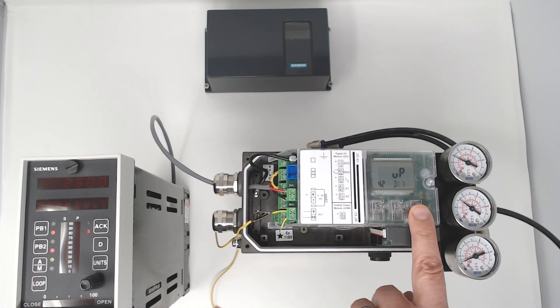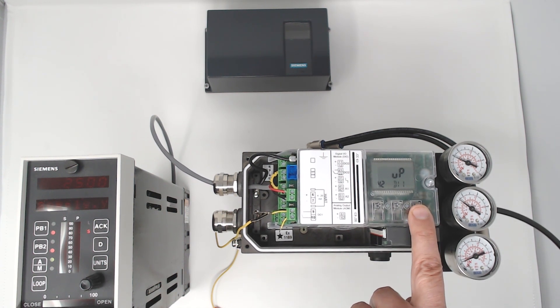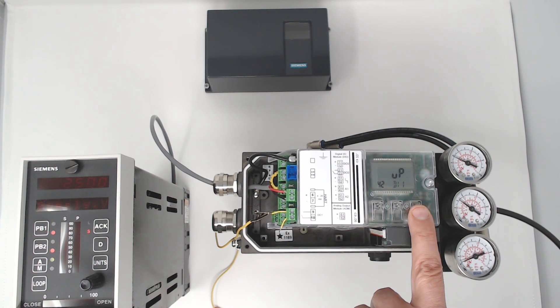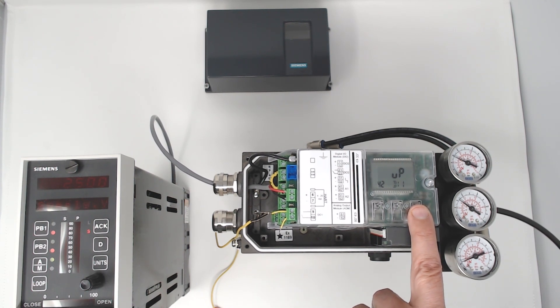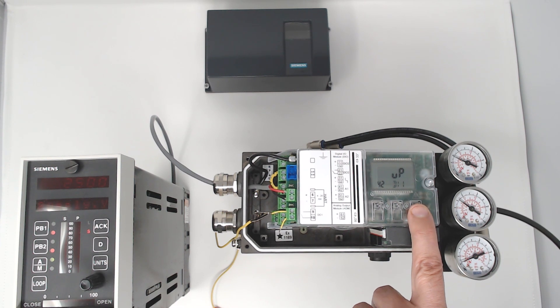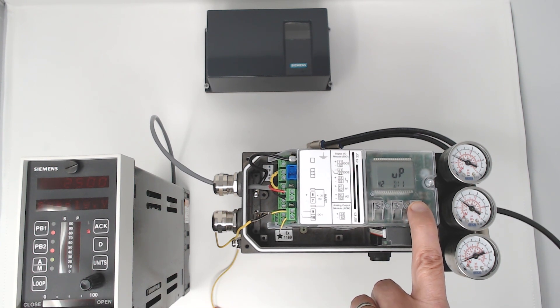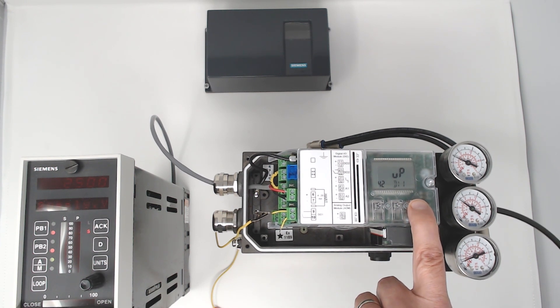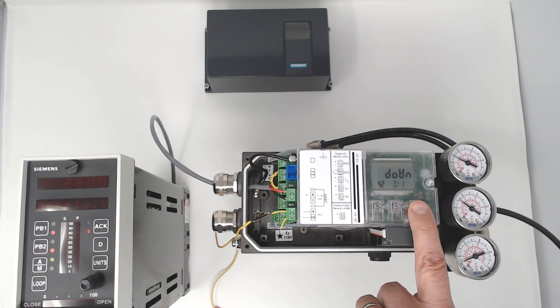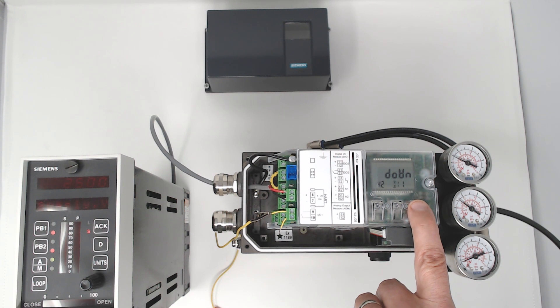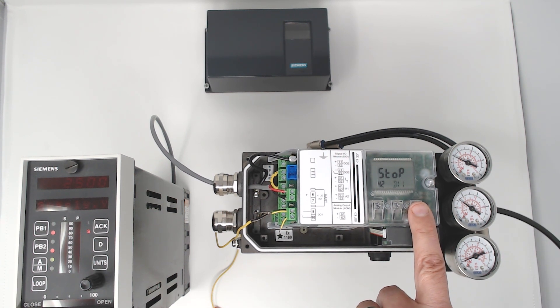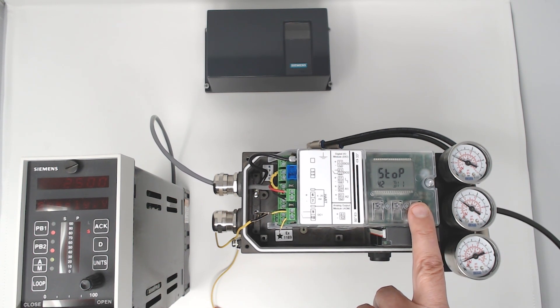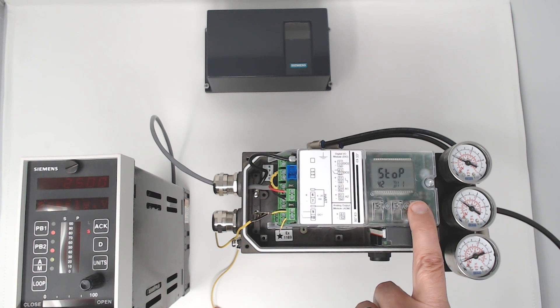Here is the override up setting. It will override the automatic control and drive the valve to the up position when the input is triggered, drive it to the down, or hold the current position, and it will hold it until the input is released.